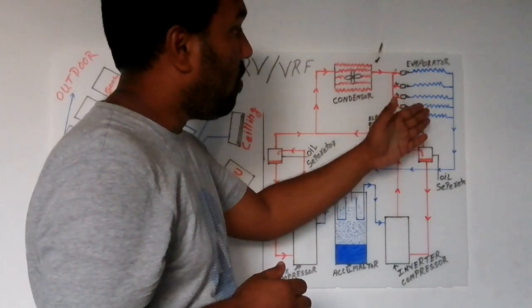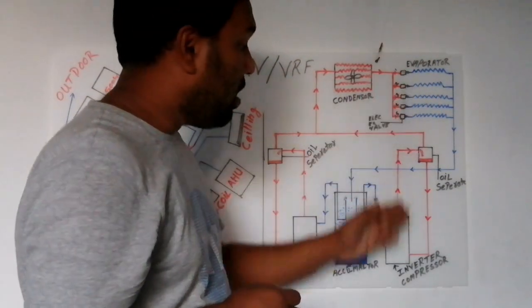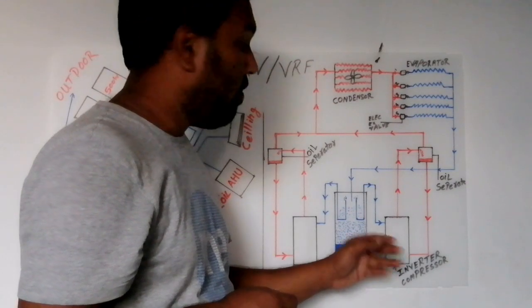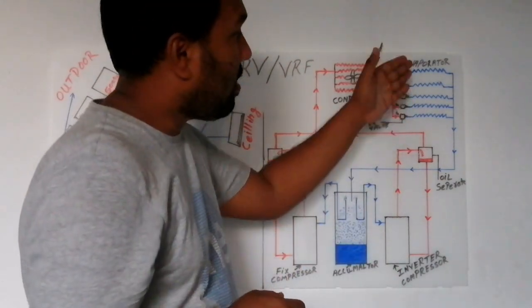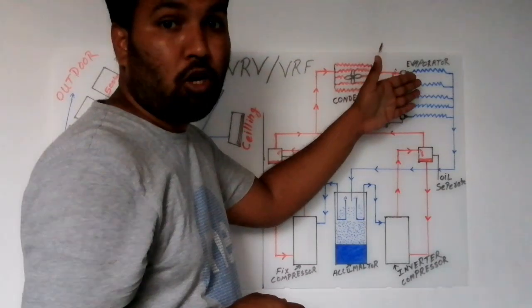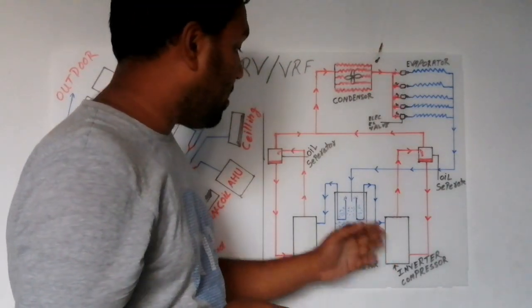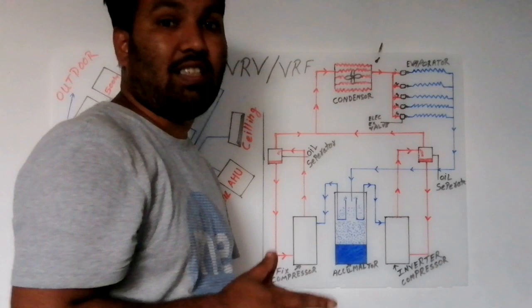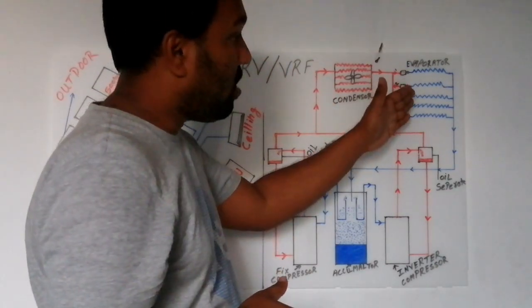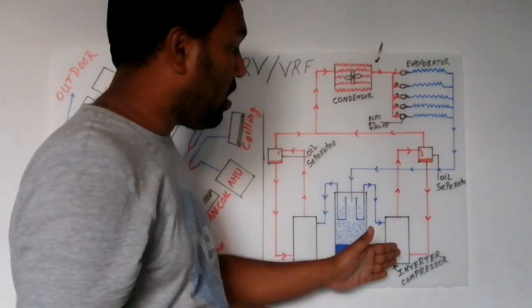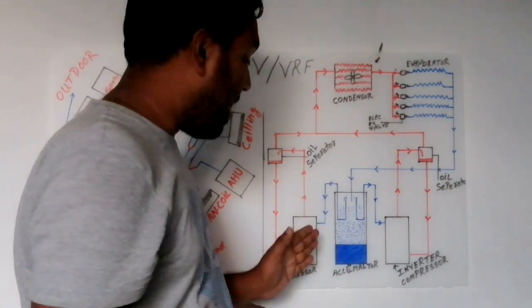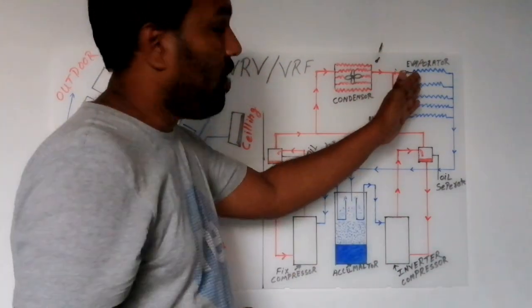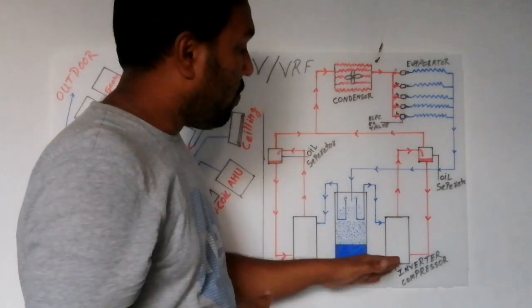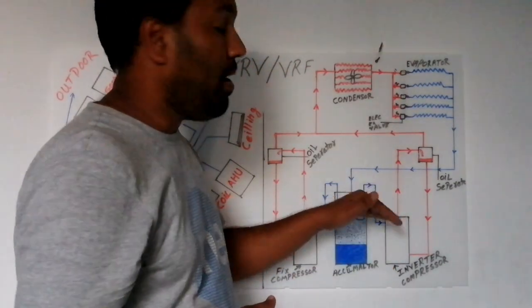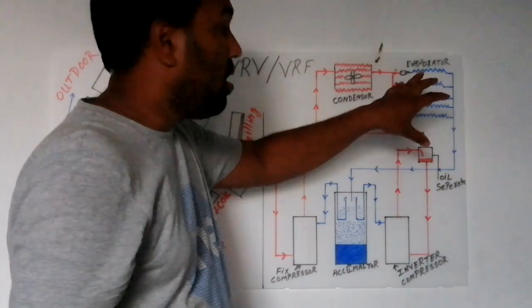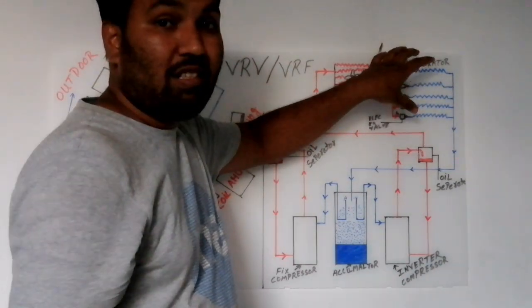If the requirement of our indoor unit is high, at that time the frequency of our inverter compressor will increase. When we start a system, if you see, the load of our evaporator coil is much higher, so our inverter compressor and fixed compressor both will work at the same time. When the temperature reaches its goal, our inverter compressor will give a command to the fixed compressor that you should stop now because we have already reached the goal. When they reach the goal, only the inverter compressor continuously works and makes the temperature stable in all the indoor units present inside our room.